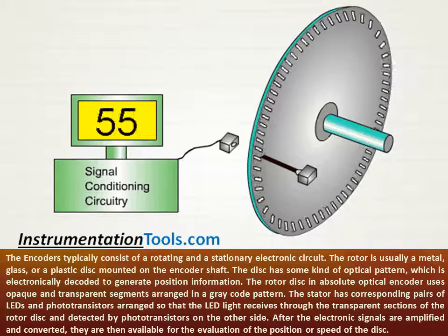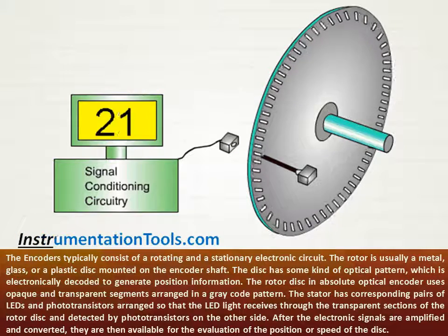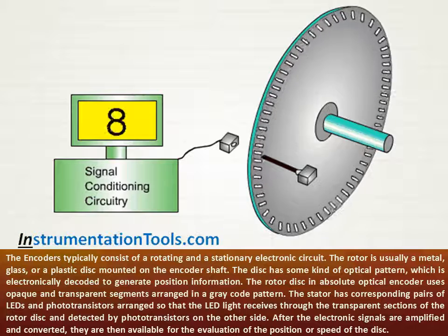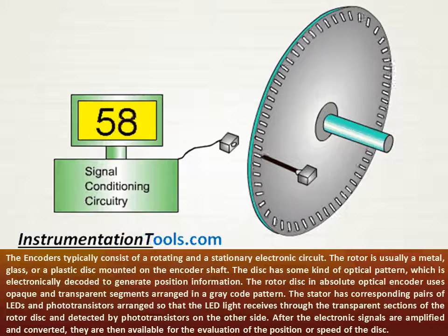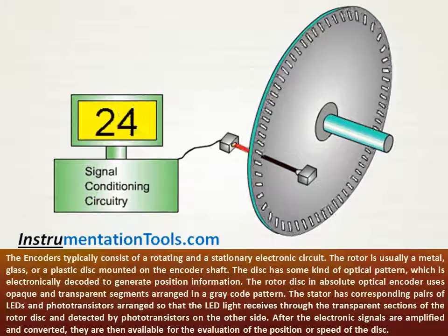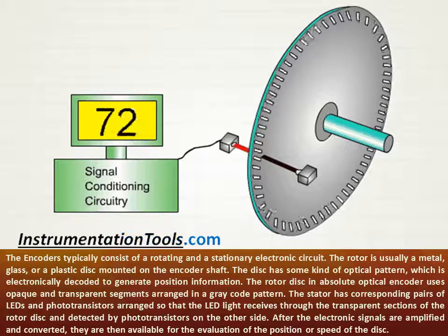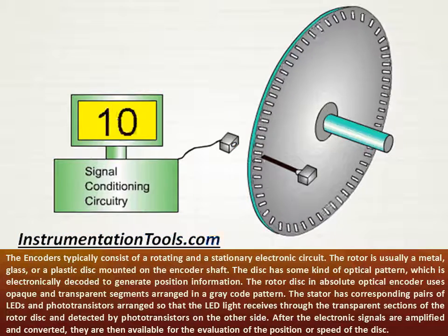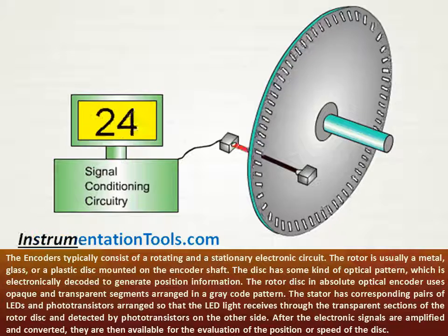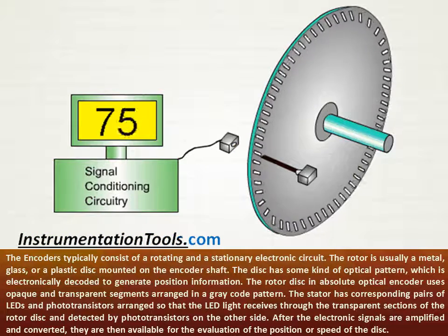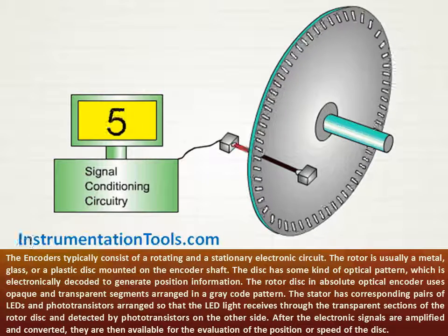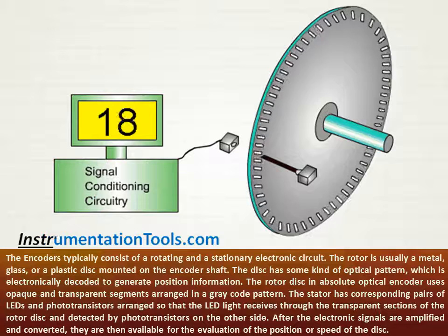The rotor disc in an absolute optical encoder uses opaque and transparent segments arranged in a grey code pattern. The stator has corresponding pairs of LEDs and phototransistors arranged so that the LED light passes through the transparent sections of the rotor disc and is detected by phototransistors on the other side. After the electronic signals are amplified and converted, they are then available for the evaluation of the position or speed of the disc.